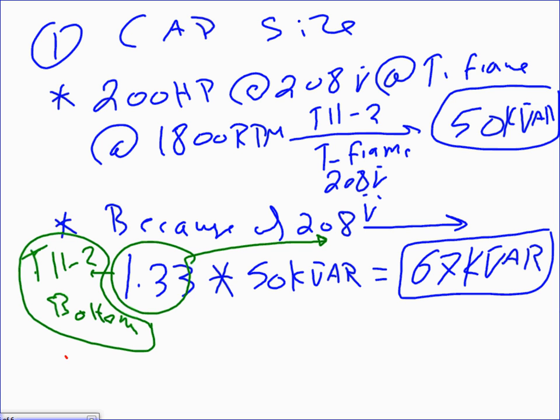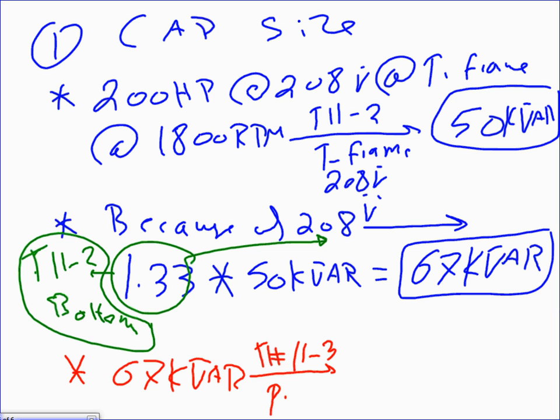So I want to take that 67K var to a table. Which table? Table number 11-3, page 167, electrical wiring, industrial. Just use this one for the smaller than 100, guys. And there's sizes for everything. So for smaller than 100, what's my next standard?